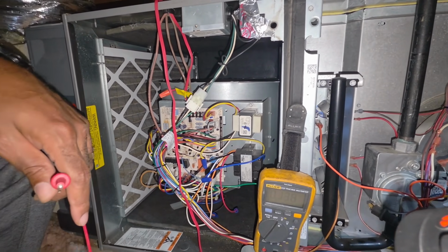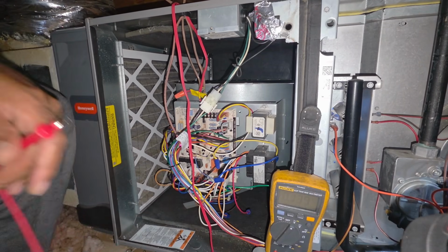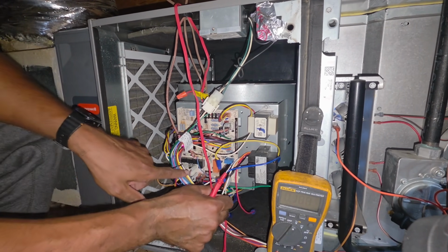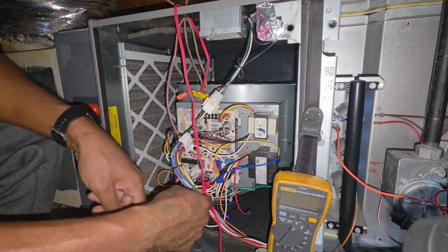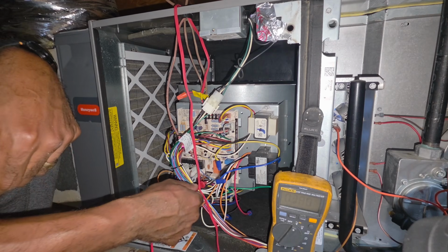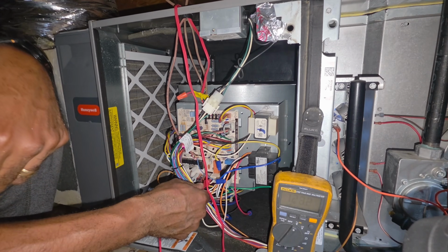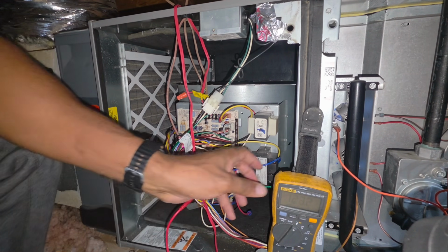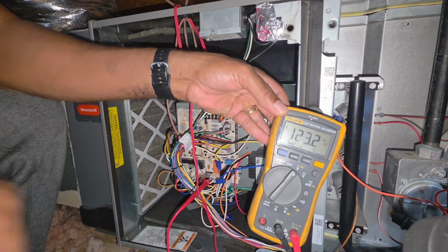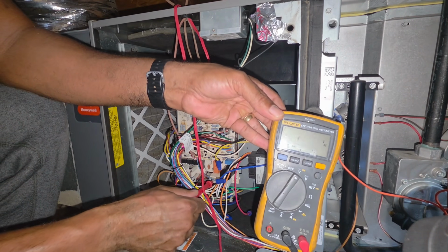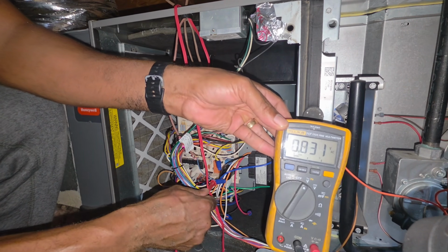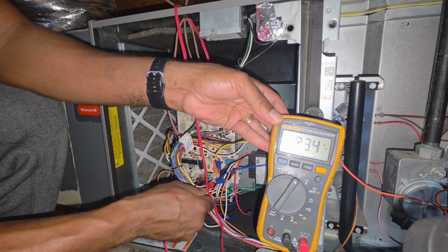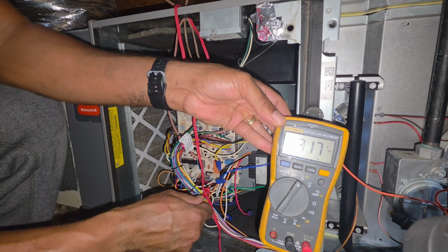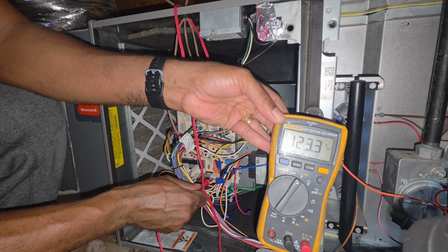All right, let's go over here. Inducer. I want to say this is the inducer right here. Let's check it. Yeah, you see we got 120. 120 on our meter. Let's go on the white one. And that's the common. Put your common to ground. So your black one, you got 120.